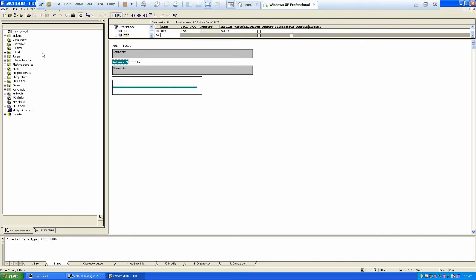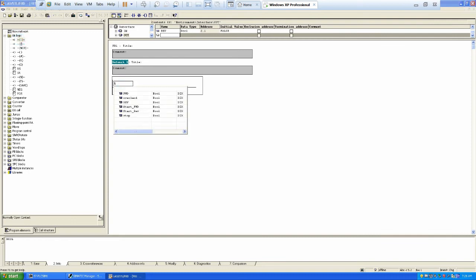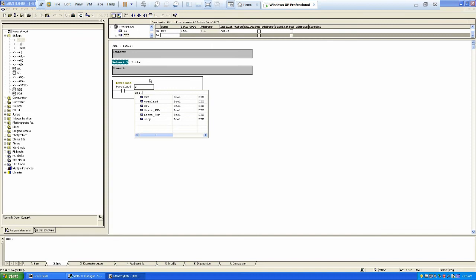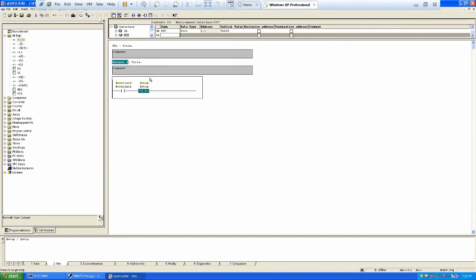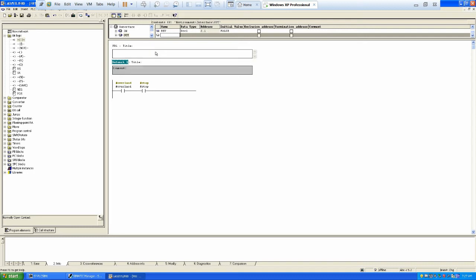Let's start to write the program. We'll take the overload in normally open condition. Why are we taking it normally open? Because we have the overload relay in the field in normally closed condition, as you can see. Then stop is also the same — we have the stop switch also in normally closed condition in the field. So we are making sure that overload and stop are not triggered in order to run the motor in forward direction. This network is for forward — we can put the comment 'Forward' here.